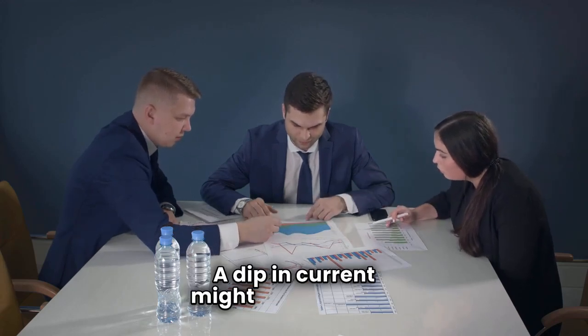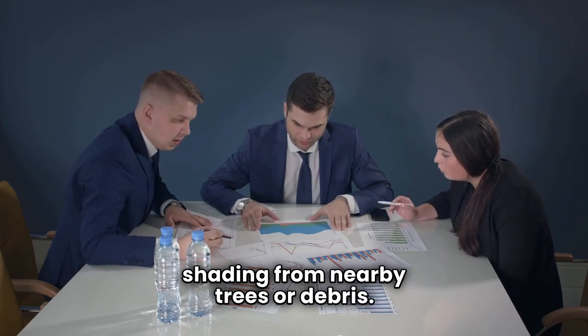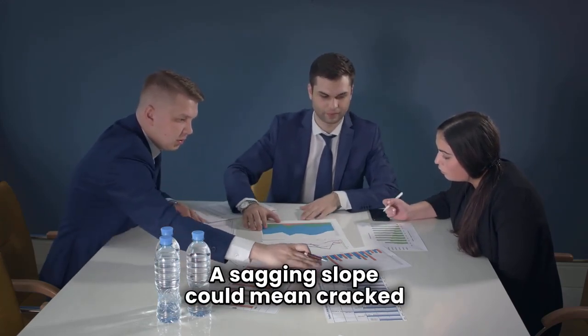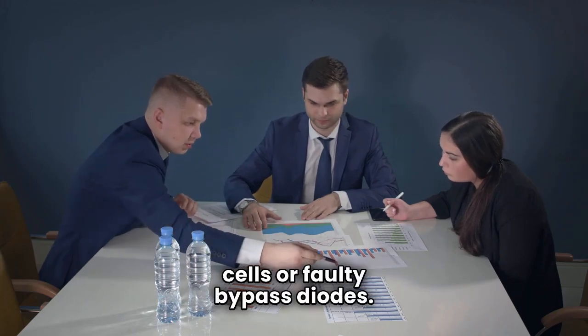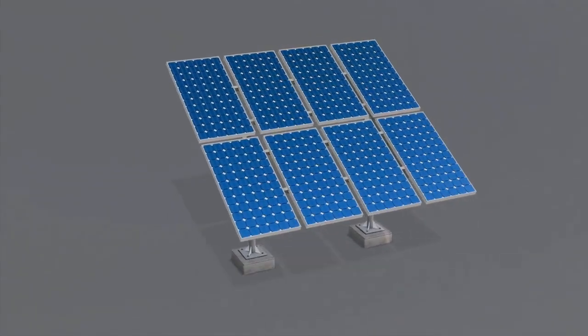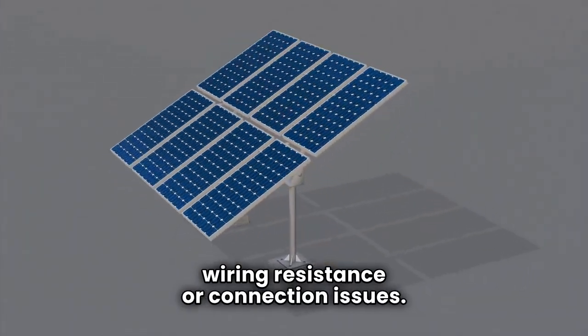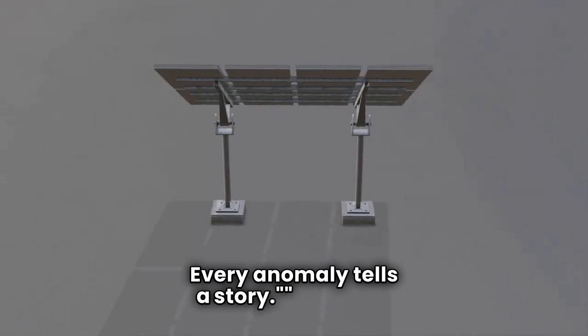A dip in current might mean partial shading from nearby trees or debris. A sagging slope could mean cracked cells or faulty bypass diodes. A shift in voltage could indicate wiring resistance or connection issues. Every anomaly tells a story.